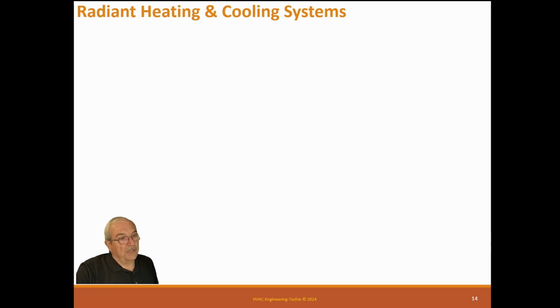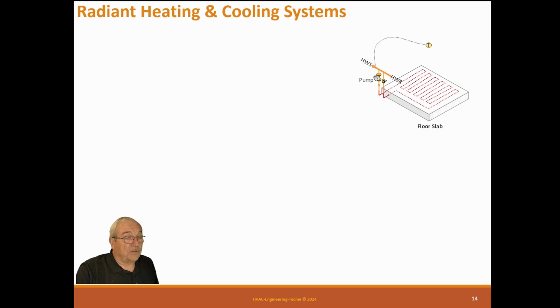So now let's look at a different system. It's not really a water-cooled system, but it is a different system. It doesn't fit in the other air handler modes. So, radiant heating and cooling. Radiant heating is where we have circuits in a slab, and we take hot water and heat the pad up during unoccupied mode, so that when it's occupied, the slab radiates heat.